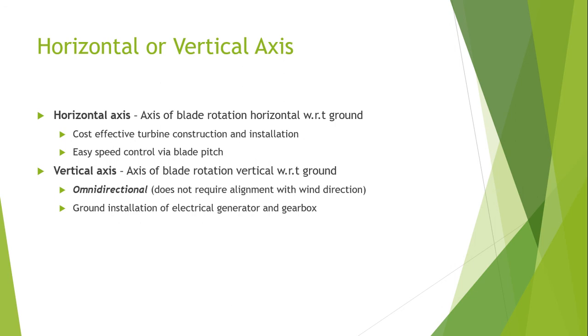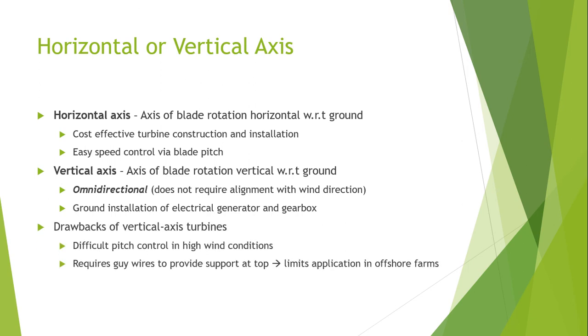In vertical axis wind turbines, ground installation of the electrical gearbox and generator is necessary, compared to horizontal axis wind turbines where the generator is mounted on top of the pole. The drawbacks of vertical axis turbines are that they have difficult pitch control in high wind conditions, require guy wires to provide support at the top, and this limits their operation in offshore applications because constant maintenance is required.